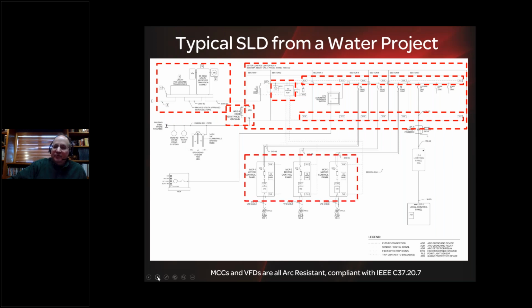Downstream, being fed from this motor control center, we see three standalone variable frequency drives in a motor control panel. And inside those drives, if you look at the bottom and the top, you'll see there's two point light sensors in each of the drive cabinets. In addition to that, there is an arc quencher annunciation panel, the same one you saw earlier in the picture.